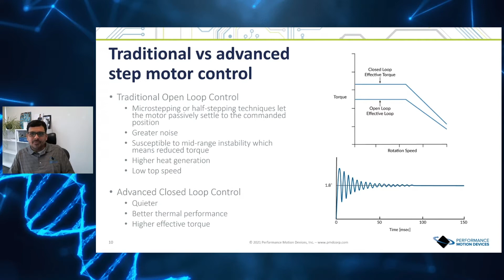The chart on the bottom shows a problem with traditional open loop control. As you do micro stepping to get to the commanded position, you have a little bit of ringing and instability. We'll look further into the reason for it, but what that equates to is higher heat generation, greater noise, and lower top speed. All of those things can be solved with advanced closed loop step control, which is quieter, gives better thermal performance, and higher effective torque.